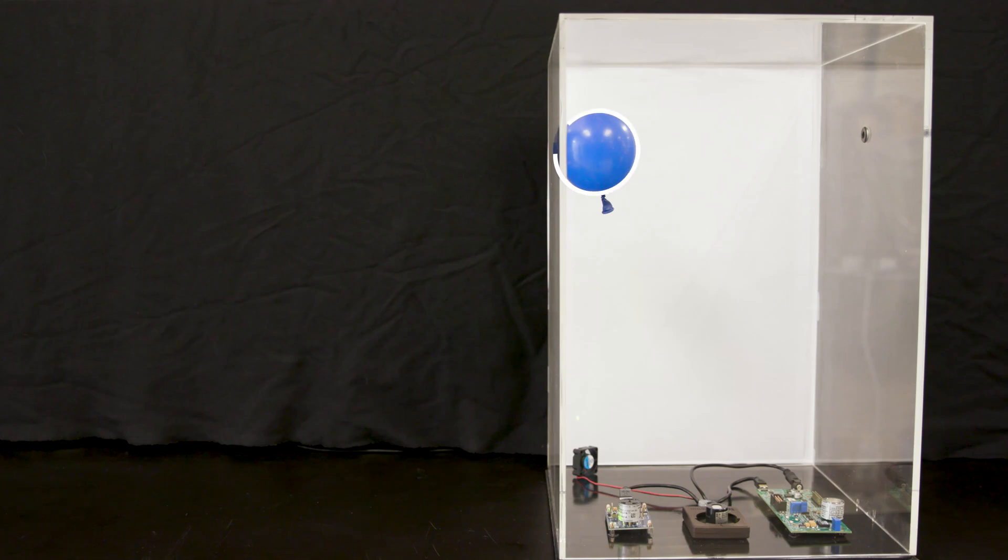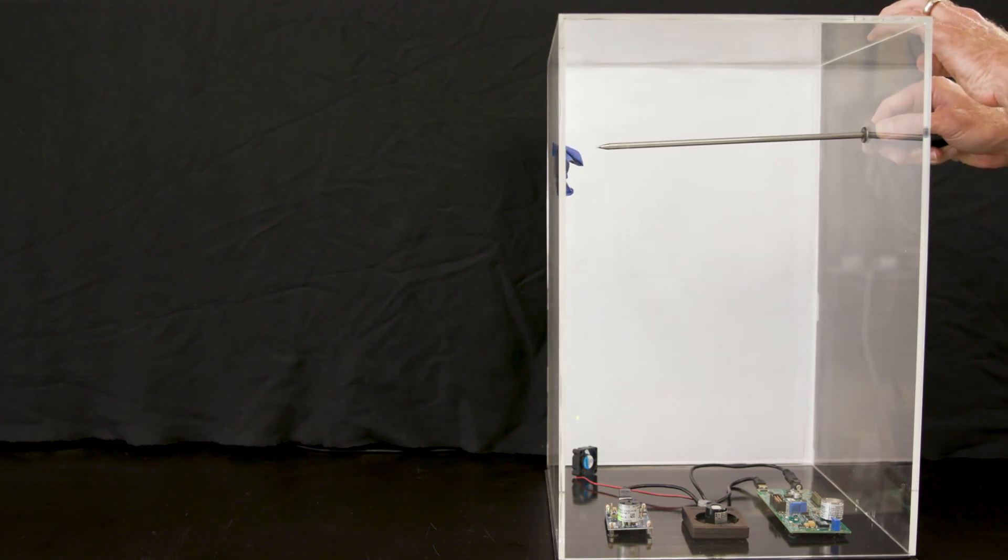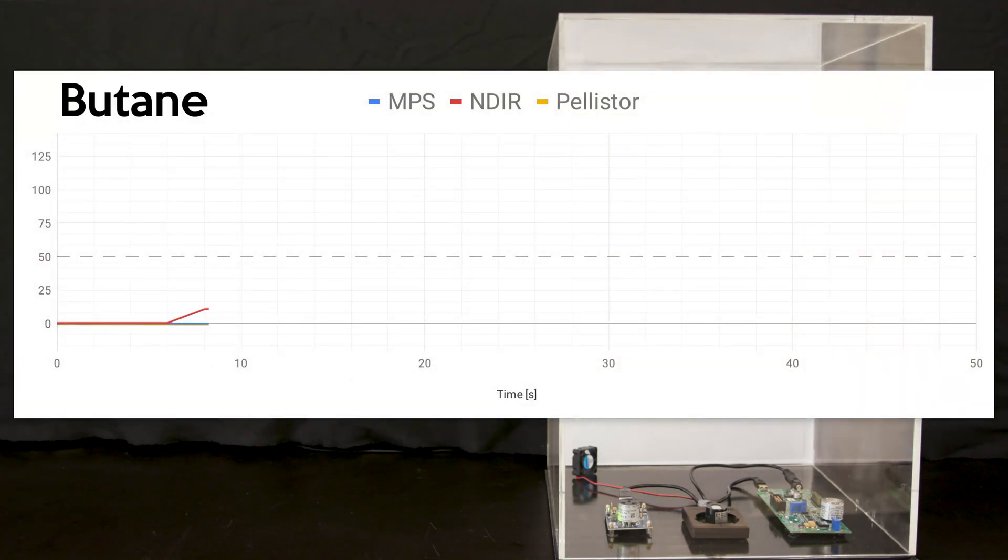Okay, next in the tank we have butane. So this is a balloon filled with the equivalent of 50% LEL butane for this particular volume. And I will pop it just like I popped the last balloon. I'll let the gas circulate in there. So butane, the MPS will be accurate for. The NDIR and the pellistor will both detect it, but will be highly inaccurate for it.